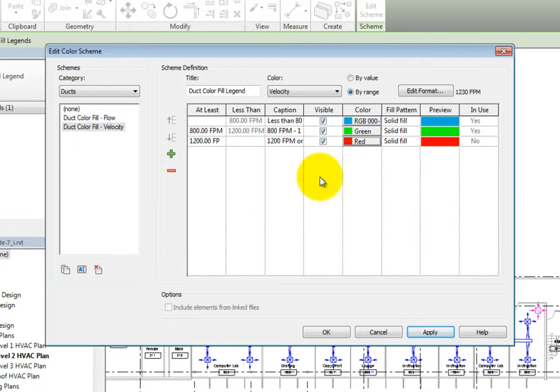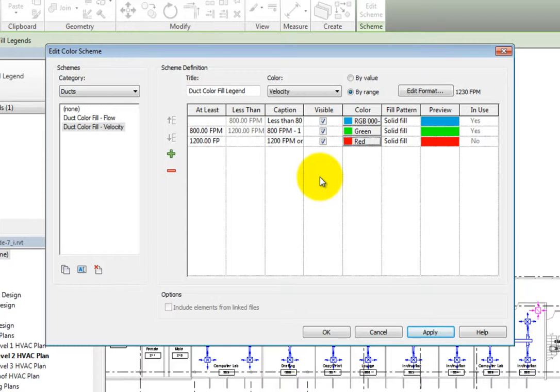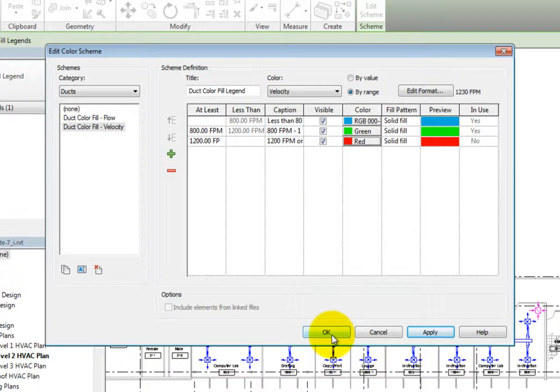At this point, this color scheme can be very useful. All the main ductwork should be green and the branch ductwork should be blue, if designed properly. If anything is red, I will need to take another look at the duct size and the airflow in the air terminals. I'll click OK to apply the color scheme and close the dialog.